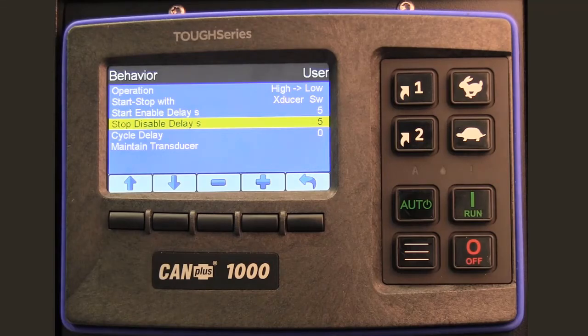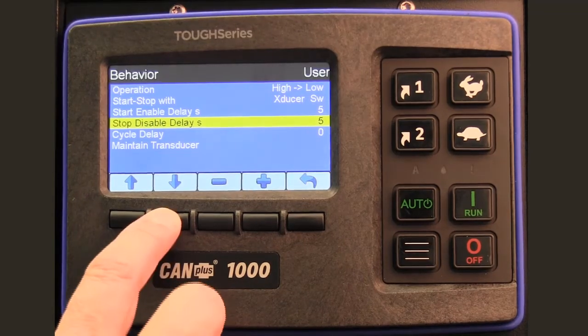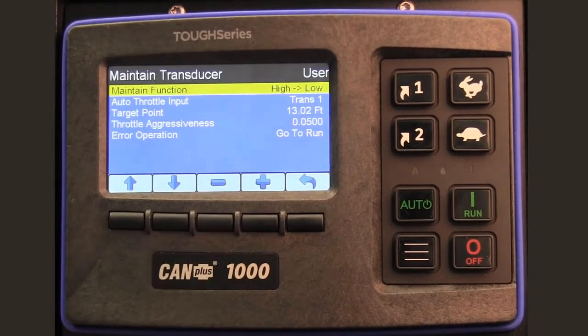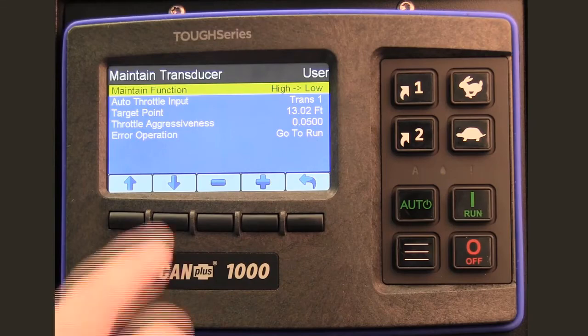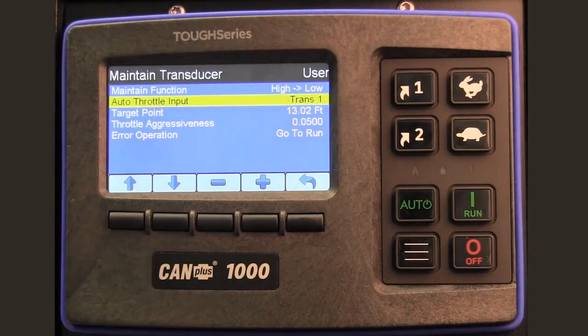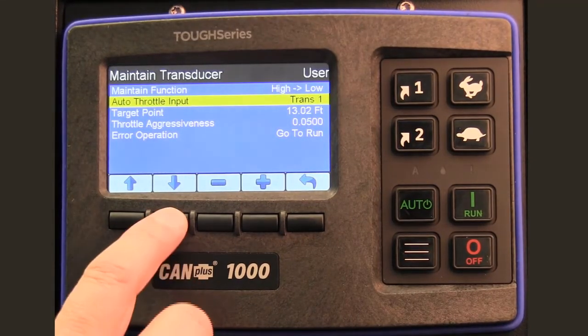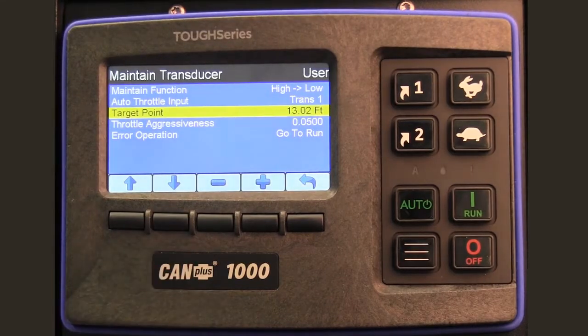This application calls for the use of the cruise control or maintain function. So the maintain level needs to be set by entering the maintain transducer menu and setting the function to high to low, auto throttle to use the transducer 1, and the target level to maintain or cruise at the desired level.